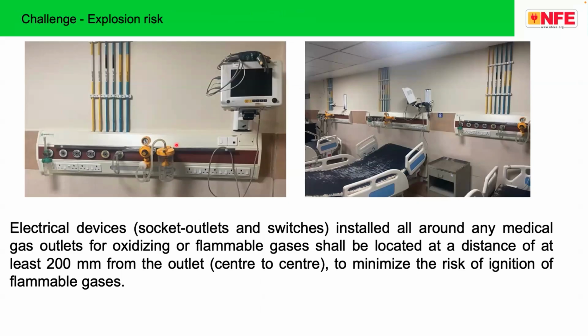The standard made several recommendations. One such recommendation is to avoid explosion. You can see here, electrical devices and the gas must be minimum 200 millimeters away. The physical distance should be minimum 200, at least 200 mm separation distance is required between these two. Medical gas outlet for oxidizing or flammable gases shall be located at a distance at least 200 mm from the outlet to minimize the risk of ignition of flammable gases.